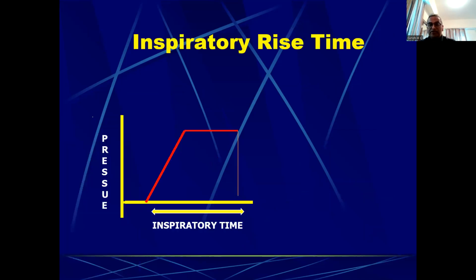Another thing you might have seen on the ventilators is inspiratory rise time. Most of the time, we don't change this parameter, but it is important to know what it is, because if we change it by mistake, it has some consequence for the patient. Basically, this is on the pressure mode. It doesn't make so much difference for the volume mode, because as I told you, in the pressure mode of ventilation, the flow is decelerating flow. You reach the peak flow and then slowly come down.